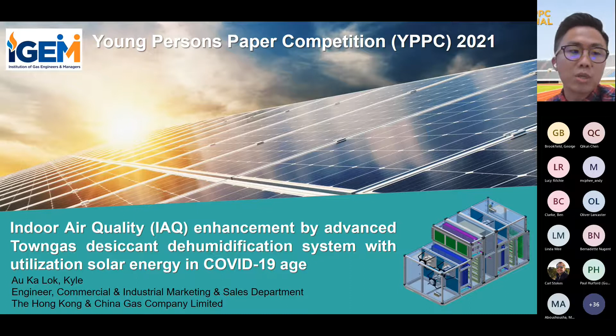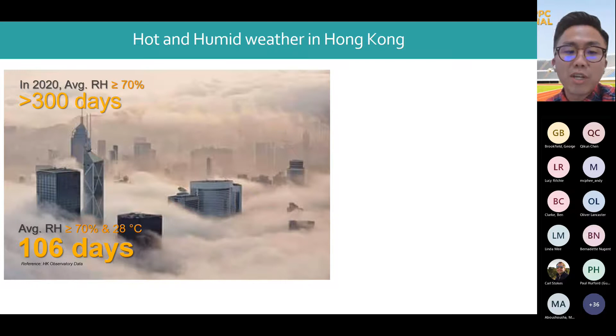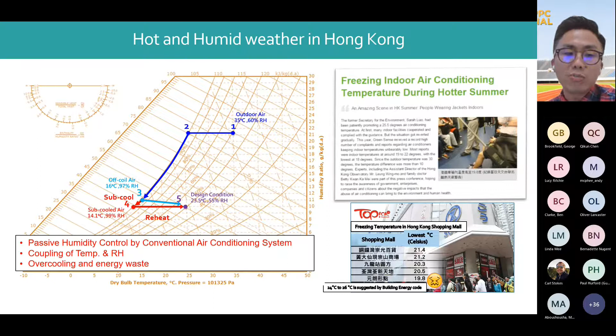Hong Kong's weather is hot and humid. According to the Hong Kong Weather Observatory, more than 300 days the average RH is larger than 70% in 2020, and over 100 days the average RH and temperature is larger than 70% and 28 degrees Celsius. Introduction of fresh air is a common way to provide IAQ enhancement and thermal comfort. However, passive humidity control by conventional air conditioning systems may result in overcooling the indoor environment and wasting energy - a typical example is the freezing indoor temperature in Hong Kong shopping malls during the hot and humid summer because of dehumidification by air conditioning systems.